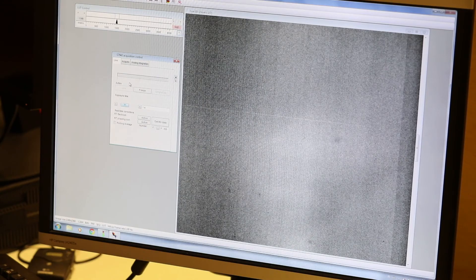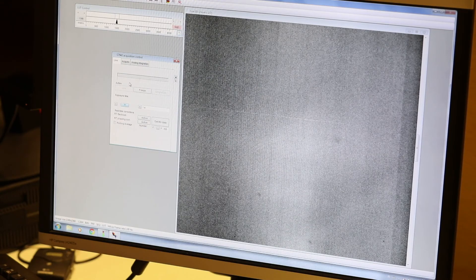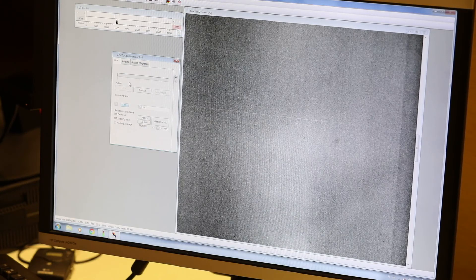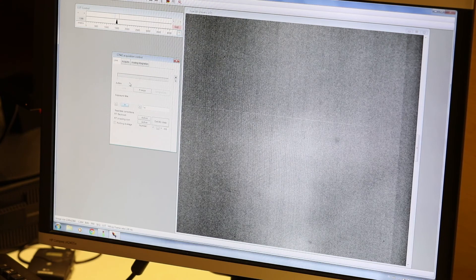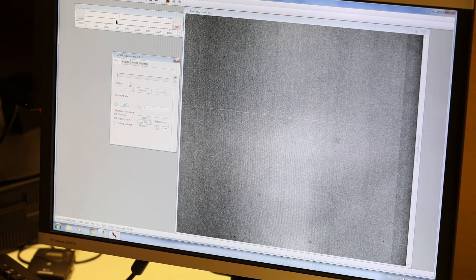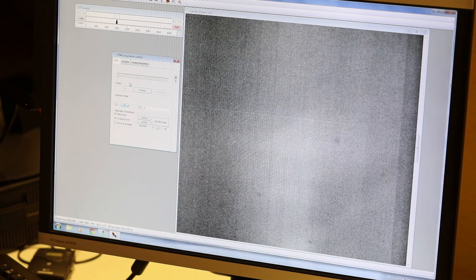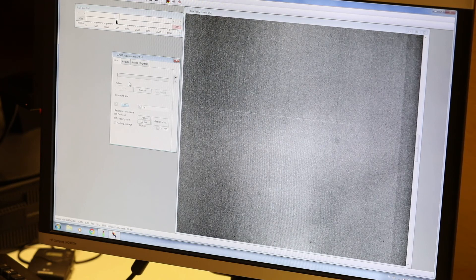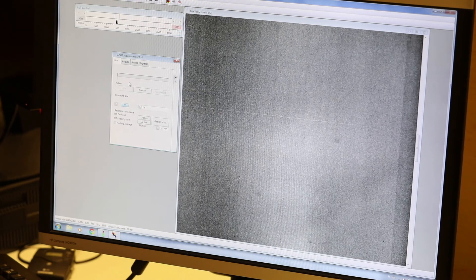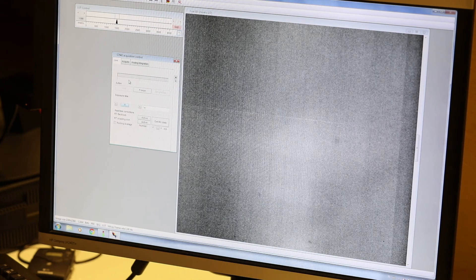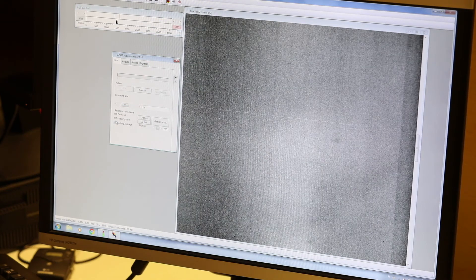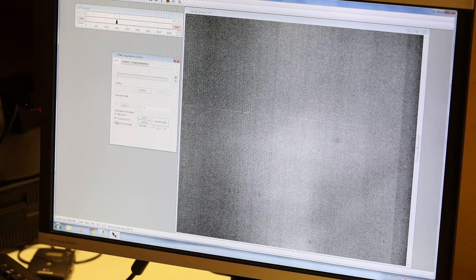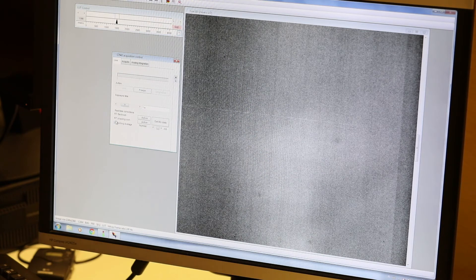Here we see the signal coming from the x-ray detector when the x-ray source is emitting radiation, but there's nothing in between the source and the detector. As you can see, the image is not uniform. The unevenness in the image is caused by variations in x-ray sensitivity in different parts of the detector. Compensating for these differences in the calibration is called flat field correction.